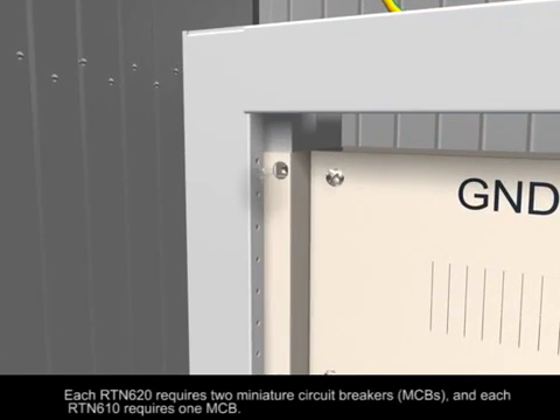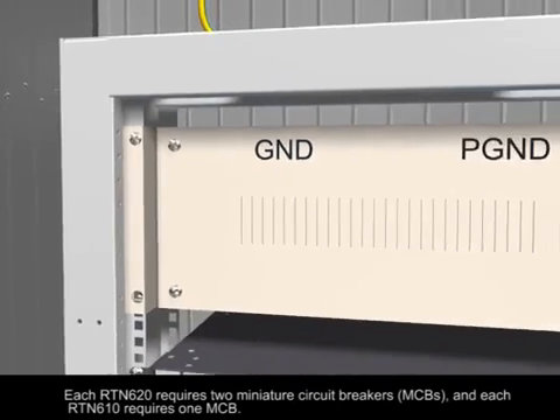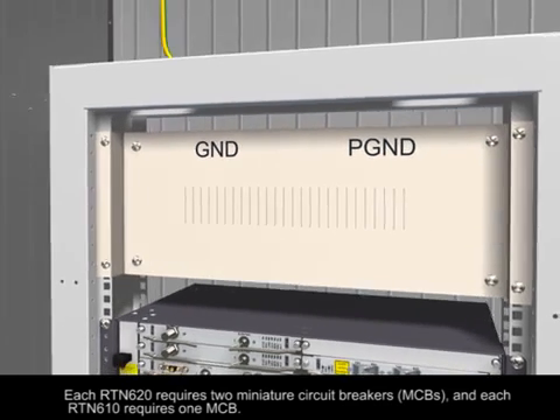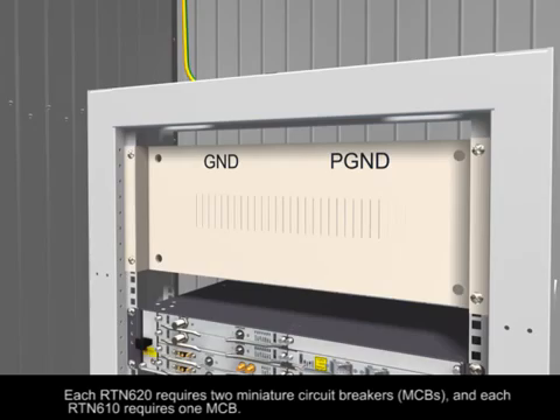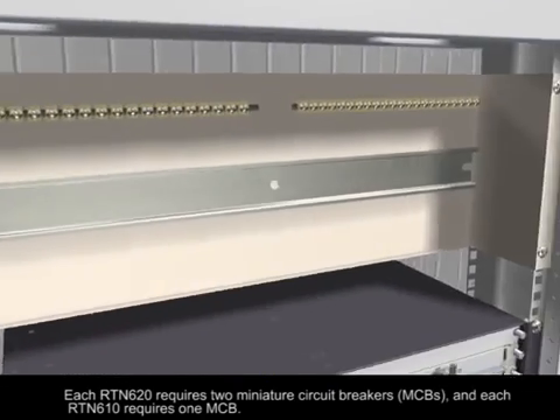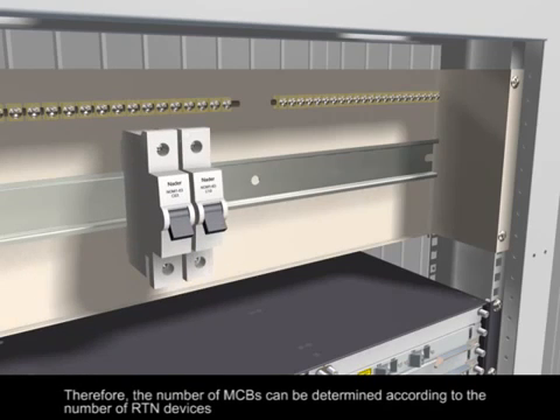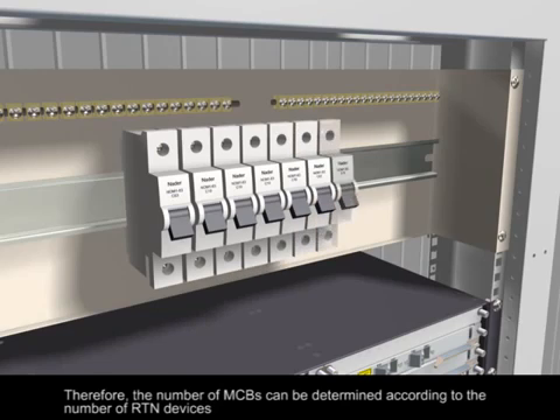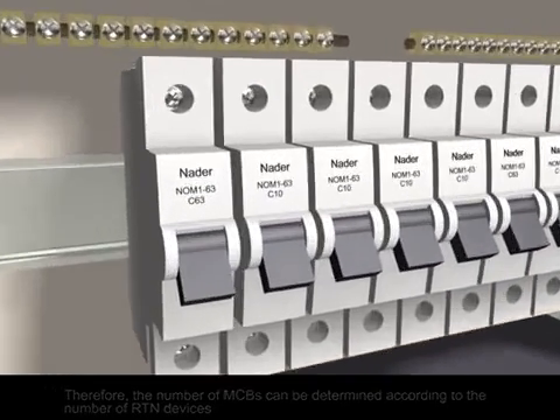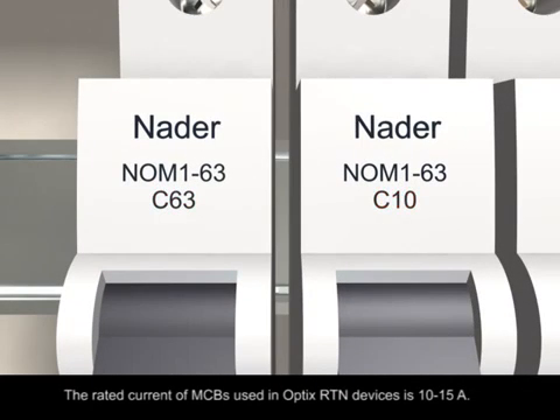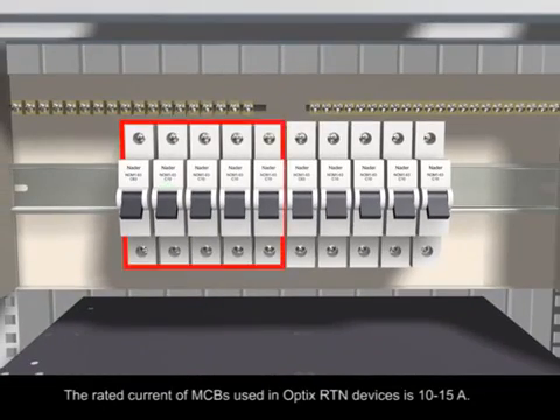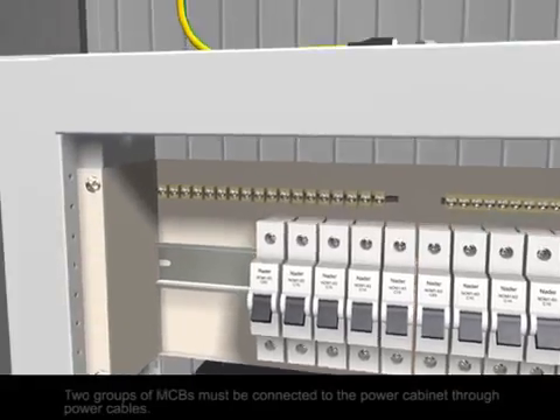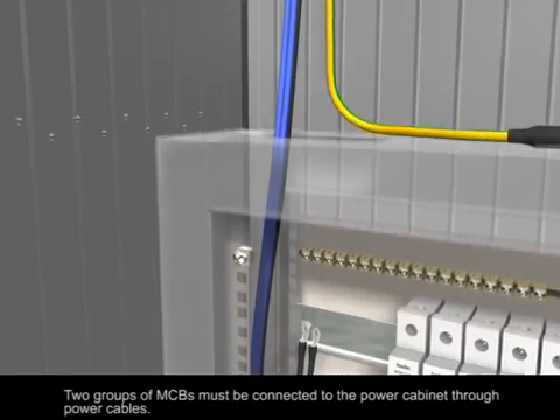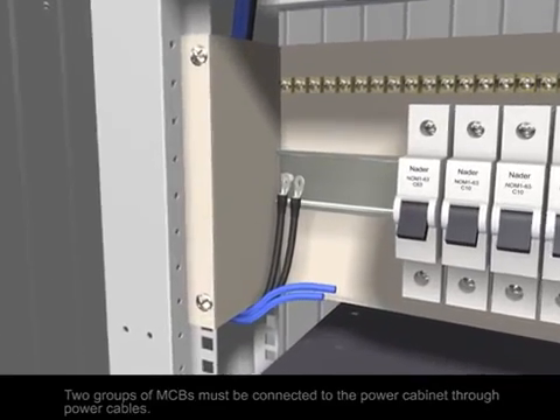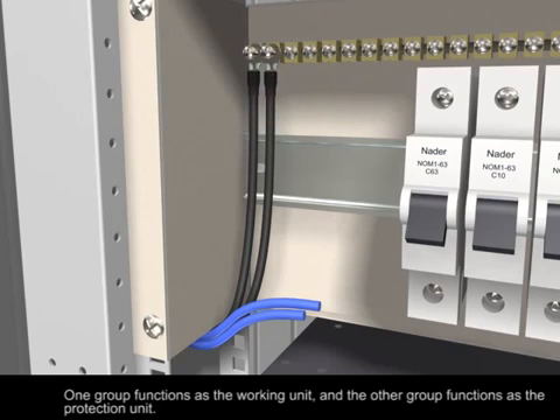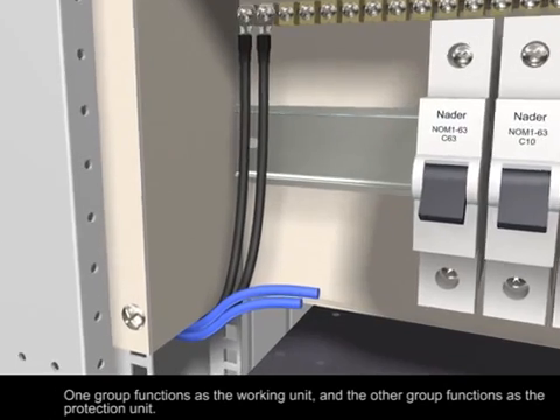Each OptiX RTN620 requires two miniature circuit breakers, hereafter referred to as MCBs, and each OptiX RTN610 requires one MCB. Therefore, the number of MCBs can be determined according to the number of OptiX RTN devices. The rated current of MCBs used in the OptiX RTN devices is 10 to 15 amperes. Two groups of MCBs must be connected to the power cabinet through power cables: one group functions as the working unit, and the other group functions as the protection unit.